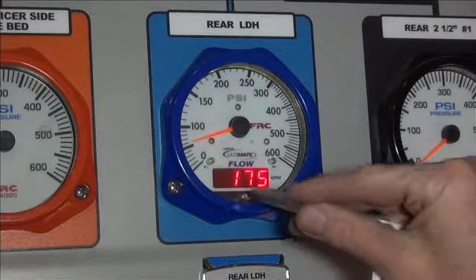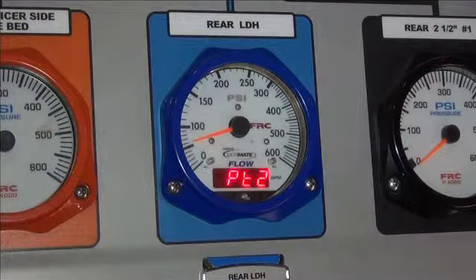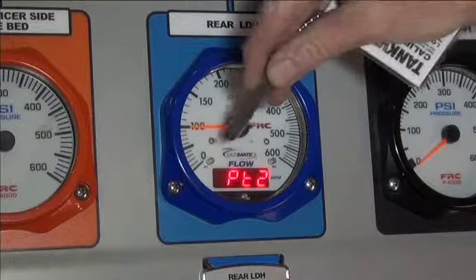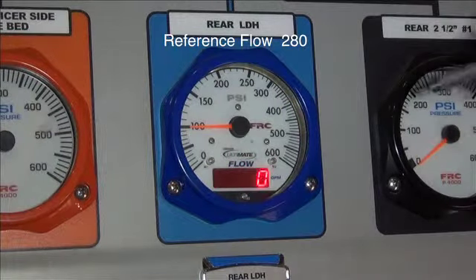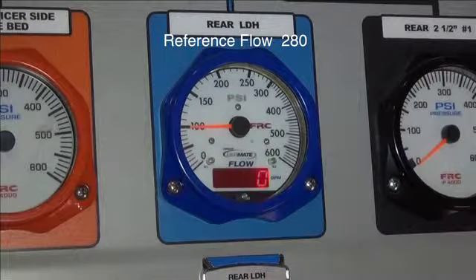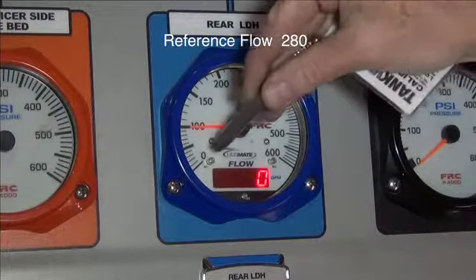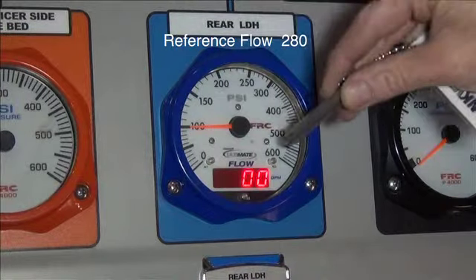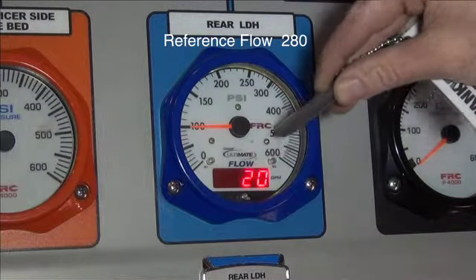Now touch the magnet to the M3 sensor briefly, and the display now shows PT2, which is the next calibration point. Change the water flow and adjust the display to the second known water flow by again touching the magnet to the M1 sensor to select the digit to change, and then touching the M2 sensor to change that digit as needed.